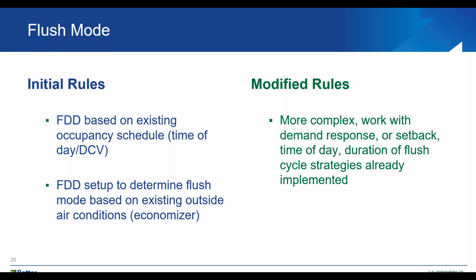Flush mode. So it's another outside air type of fault. A lot of conditions in the early morning where you may want to set it up to run, flush the building with 100% outside air for a short period of time to pre-cool it essentially. Or you may want to flush the system, the building based on occupancy. Well, they're coming at 8 o'clock in the morning, or even in the middle of the day if you have an opportunity to flush the systems.